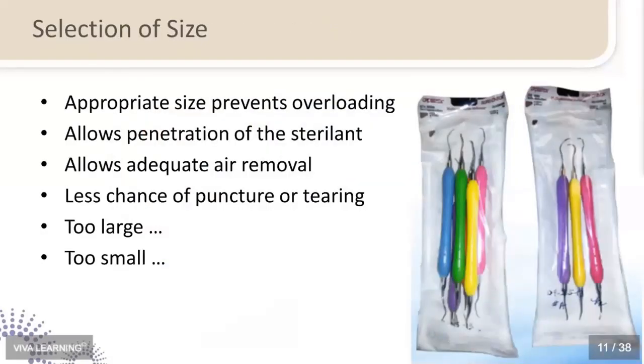We need to think about size because it is recommended in our practices that we have multi-size pouches available depending upon the type of instrumentation sets that we're going to be using with our pouches. You want to make sure that you're preventing overloading, because if you put too many instruments in, like the picture you see on the left, what's going to happen when that pouch expands, obviously the length is going to shorten a little bit, and so the likelihood that you're going to have instruments poking through the paper side and compromising the integrity of that paper, you can't use that pouch. If you overfill it, you're going to breach the pouch.